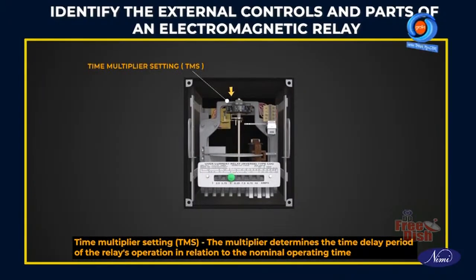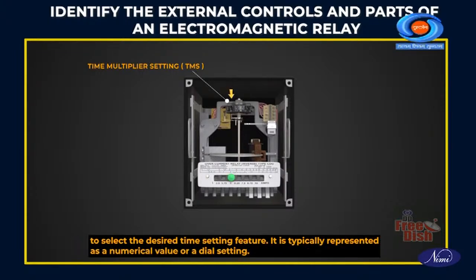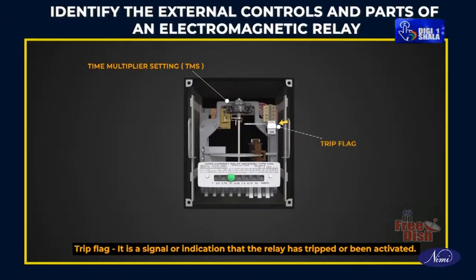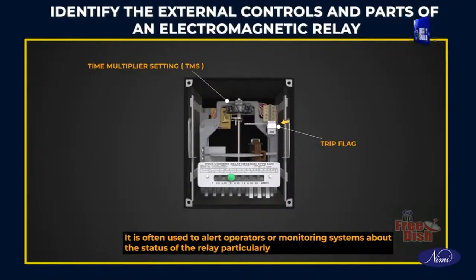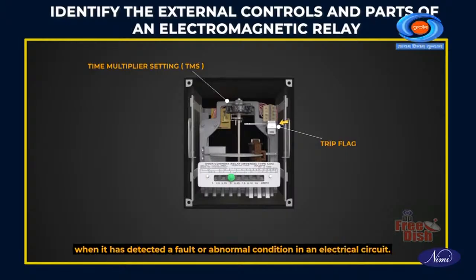Time multiplier setting. The multiplier determines the time delay period of the relay's operation in relation to the nominal operating time to select the desired time setting feature. It is typically represented as a numerical value or a dial setting. Trip flag. It is a signal or indication that the relay has tripped or been activated. It is often used to alert operators or monitoring systems about the status of the relay, particularly when it has detected a fault or abnormal condition in an electrical circuit.